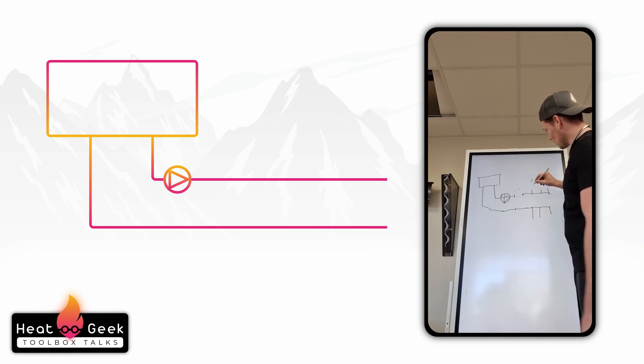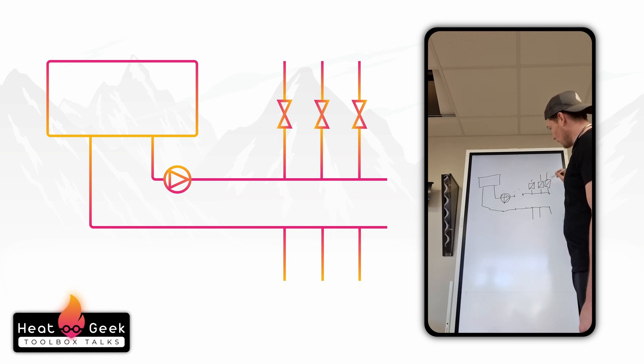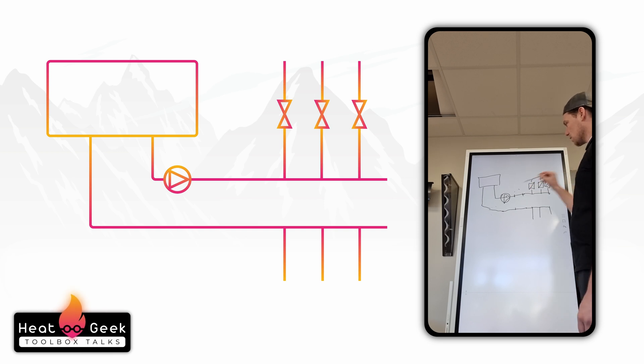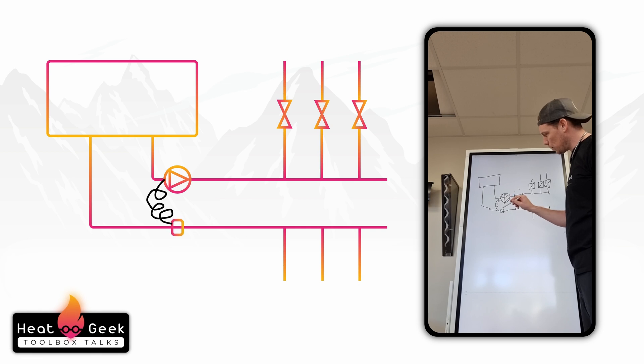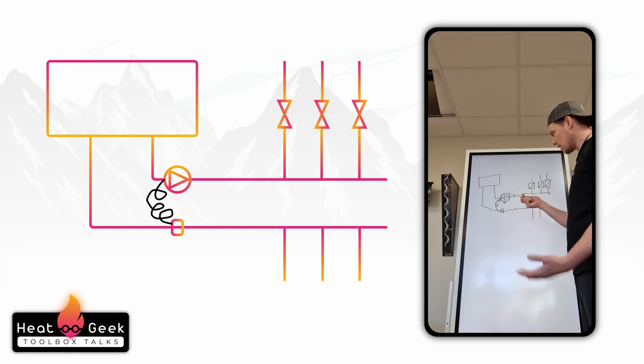And just put good old-fashioned zone valves in which don't look as sexy for social media. Then if you put that on proportional pressure, that will vary its flow rate accordingly to the zones being open. Or even better, get a DT pump and put a sensor on here and that will rectify for whatever DT you set depending on the load on the system.